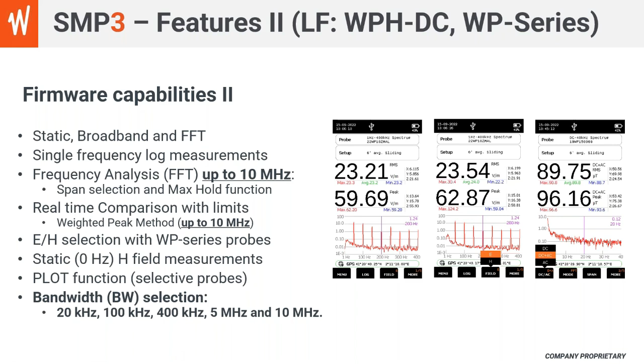For example, railway requires you to measure up to 20 kilohertz, so you have the 20 kilohertz bandwidth. You also have 100 kilohertz. You have 400 kilohertz for household appliances and automotive applications, 5 megahertz for the IEEE low frequency assessment, and 10 megahertz for ICNIRP, the ARPANSA limit, Safety Code 6, all these different standards. You have different selections to correctly configure the frequency range to measure within the specified ranges as given in the standards.